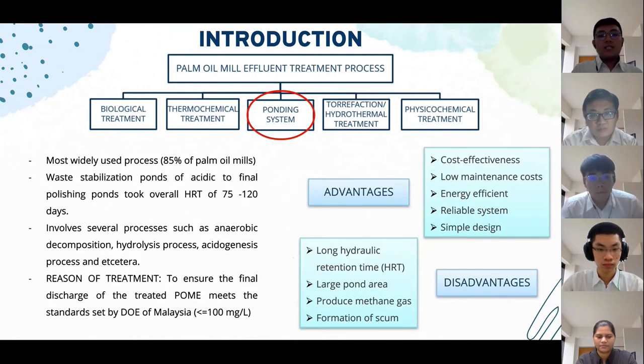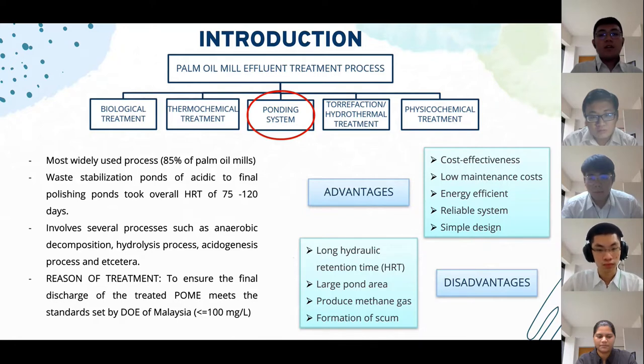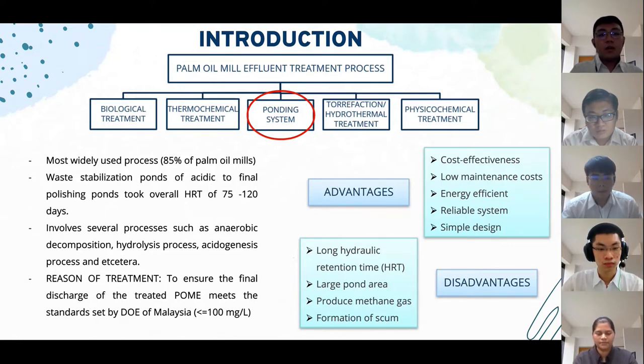The ponding system is widely used in Malaysia due to several advantages. It is inexpensive and easy to handle in terms of its simplicity and low operational maintenance. It is also energy efficient, as no mechanical mixing or complex operational control and monitoring is required. However, it does have several shortcomings: the hydraulic retention time is long, a larger area is needed, and methane gas is produced throughout the process, which contributes to the greenhouse effect.